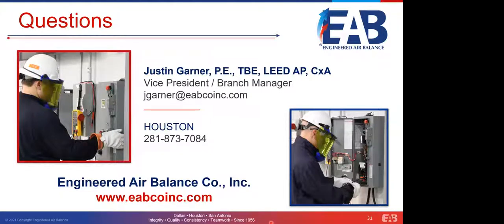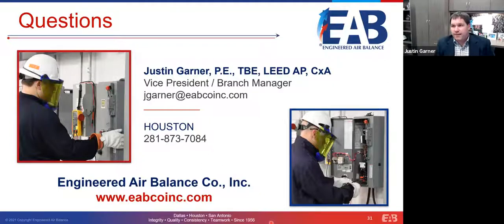Okay, the next one is indirect drive fan. The manufacturer put the RPM design on the nameplate of the motor, but on the nameplate of the fan, we found a different RPM. Which one of them is the correct one? Depending upon the manufacturer, normally the equipment manufacturer's tag is going to be the correct designation. Without knowing more information than what was submitted, that's normally the standard answer.